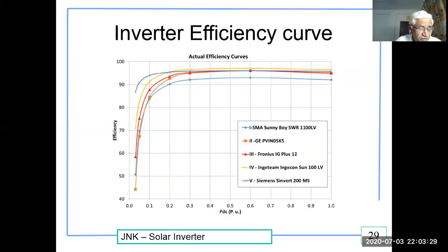Now, inverter efficiency is the most important. As every power processing stage expends power itself, solar inverters are expected to be as efficient as possible. This is because we wish to deliver the maximum PV generated power to the load or the grid. Typical efficiencies are more than 95% at rated conditions. Depending on the topology, the inverter is expected to have built-in MPP trackers.